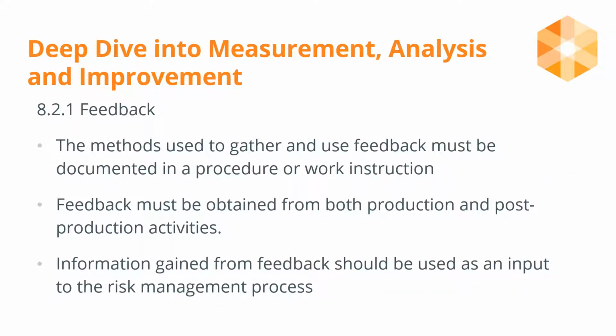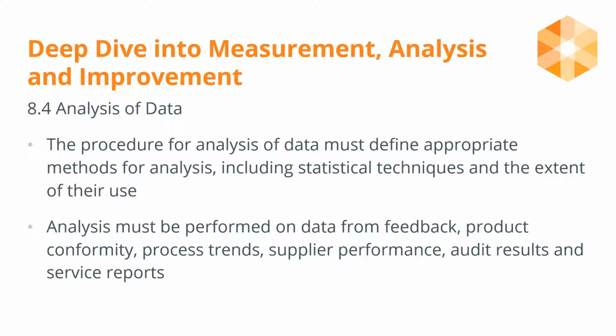Methods must be documented for gathering and using feedback, which must be obtained from activities both during and post-production. Information obtained from feedback should be applied to the risk management process. The data analysis procedure must define appropriate analysis methods, including statistical techniques and the extent of their use. Analysis must be performed on data from feedback, product conformity, process trends, supplier performance, audit results, and service reports.